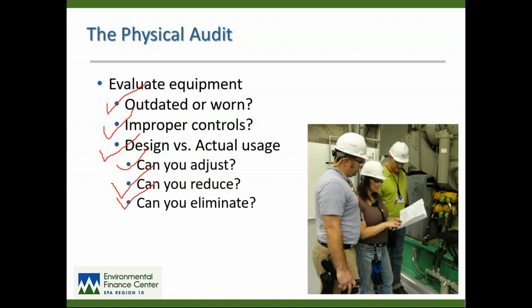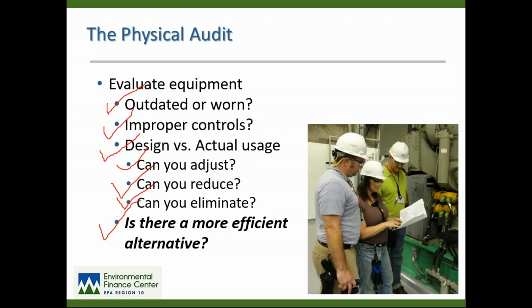If you've got a whole treatment area with high bay lighting way up on the ceiling that has 4 fluorescent tubes, can you take 1 or 2 of those tubes out for each of the fixtures, and again, still not compromise employee safety and so forth? And then ask yourself, among all the different alternatives that are out there, especially now with LED lighting becoming more reliable and less expensive, is there a more efficient alternative? And in terms of pumps and motors, there almost always is. And with lighting also.